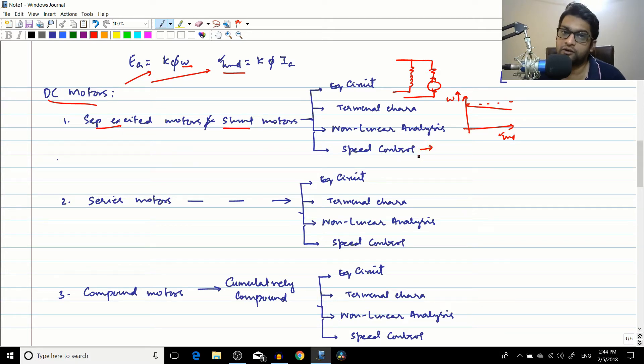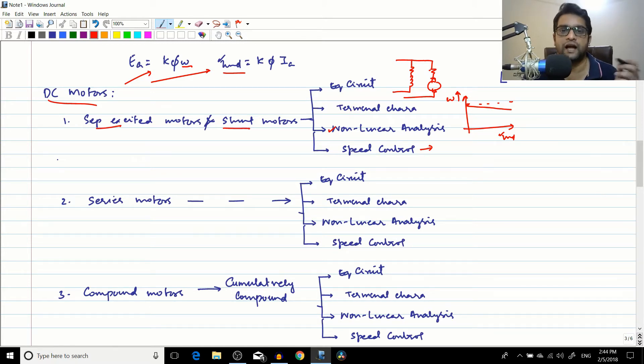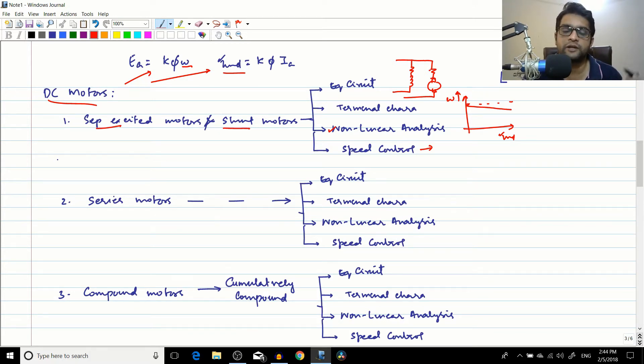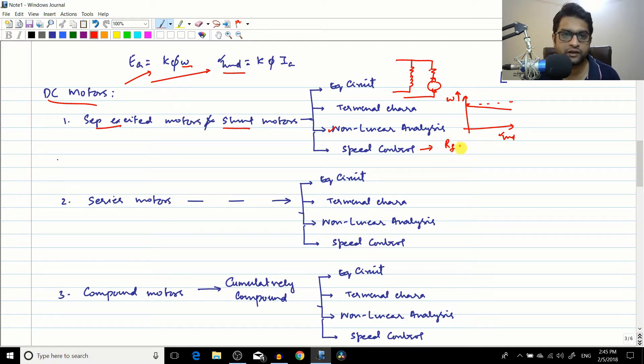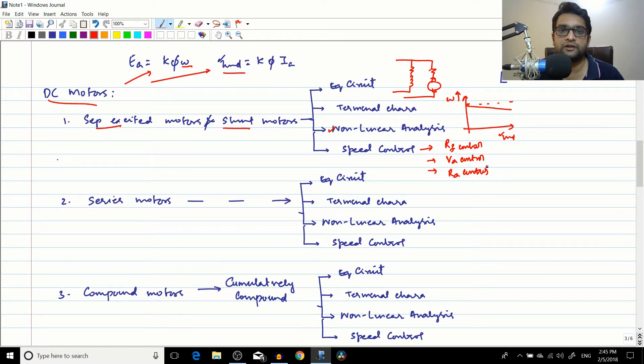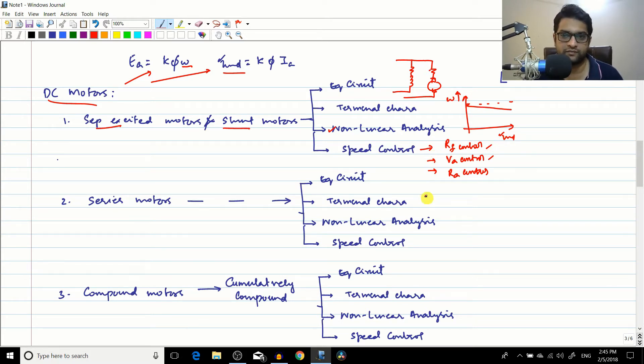Based on the terminal characteristic, different methods of speed control were studied. Non-linear analysis involved accounting for armature reaction and flux weakening effects in problems. For shunt motors, speed control methods included field resistance (Rf) control, armature voltage control, and armature resistance control — though the last method is wasteful as it dissipates power as heat, so mainly the first two were used.